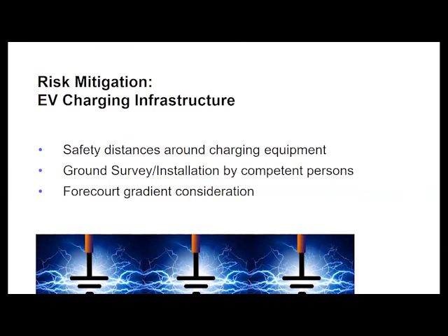The other thing to consider when mitigating risk on a forecourt is the gradient. Forecourt gradients are designed so that fuel falls or flows towards some form of interceptor. So consideration should be given as to whether the charging equipment is located in a place where petroleum vapor may gather due to the gradient of the forecourt. The danger is a potential atmosphere could form around or near the base of the charging equipment. And on that, it's not acceptable as a fix to simply raise the charging equipment onto some kind of concrete plinth or something like that, because it doesn't take the flammable atmosphere away. It would still gather there.